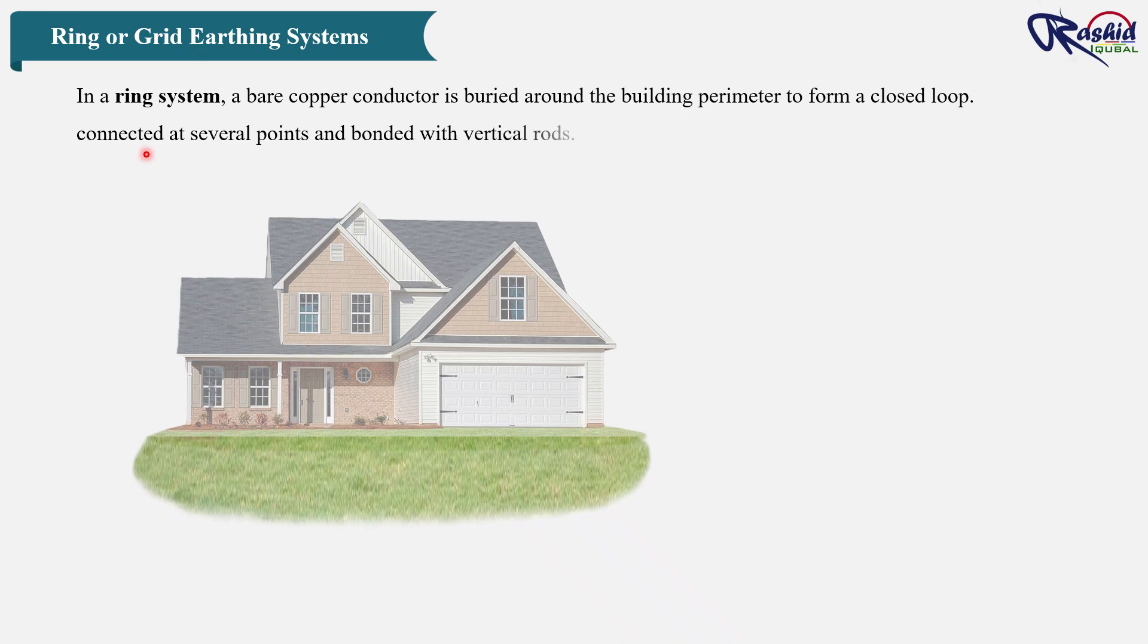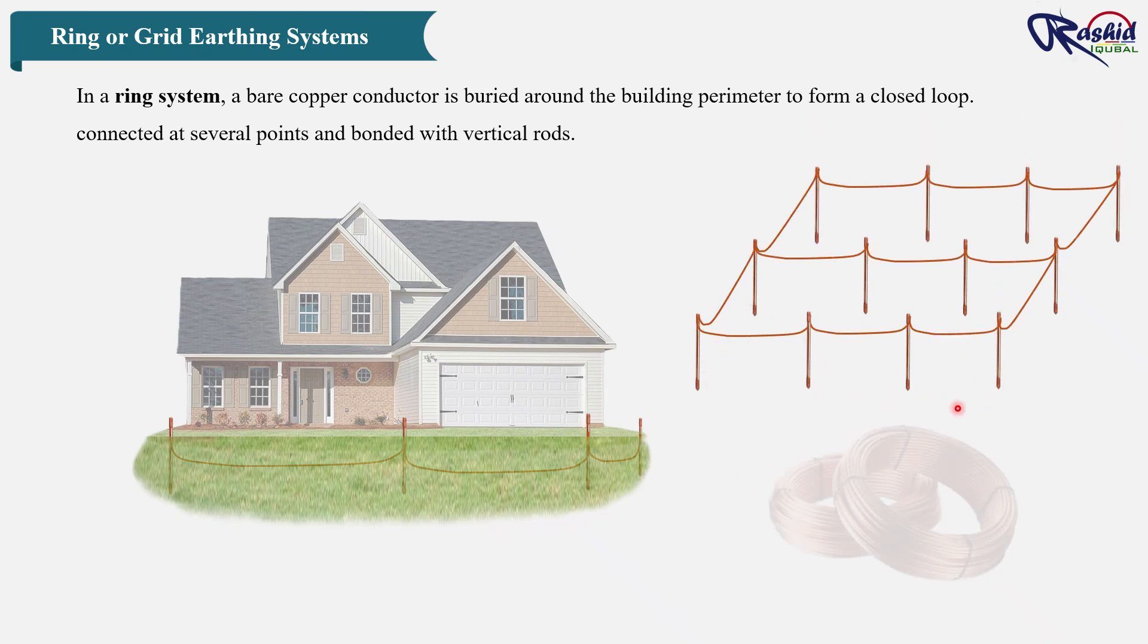Ring or grid earthing system. For large commercial or industrial buildings, we often use ring or grid earth systems. In a ring system, a bare copper conductor is buried around the building perimeter to form a closed loop. For better performance, a grid of conductors is laid under the soil, connected at several points and bonded with vertical rods.